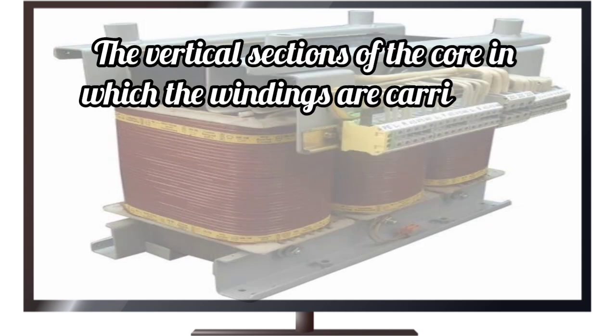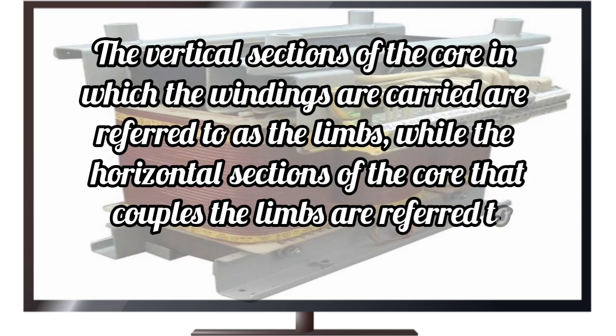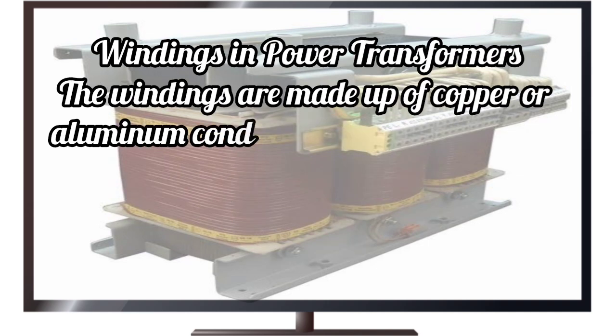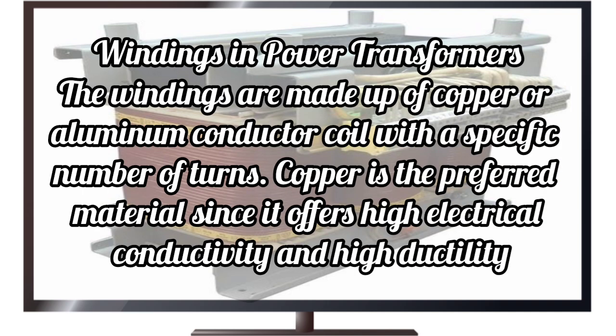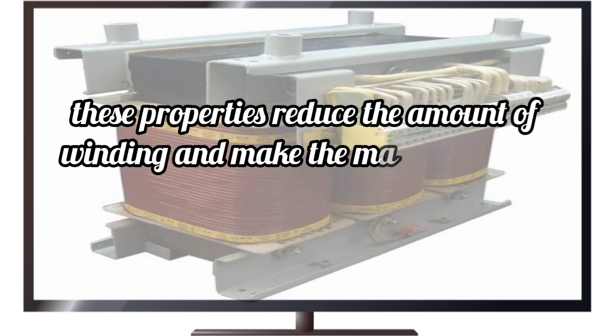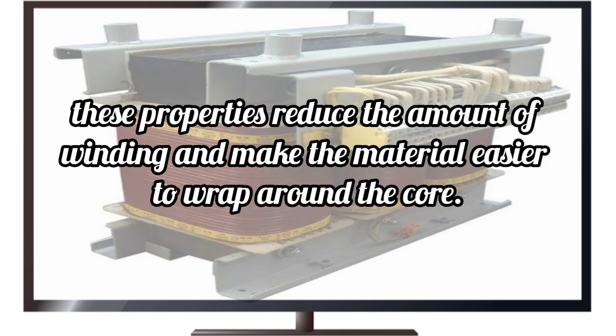The vertical sections of the core in which the windings are carried are referred to as the limbs, while the horizontal sections of the core that couple the limbs are referred to as the yokes. Windings in power transformers. The windings are made up of copper or aluminum conductor coil with a specific number of turns. Copper is the preferred material since it offers high electrical conductivity and high ductility. These properties reduce the amount of winding and make the material easier to wrap around the core.